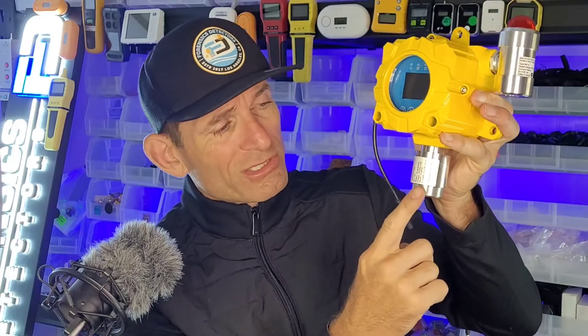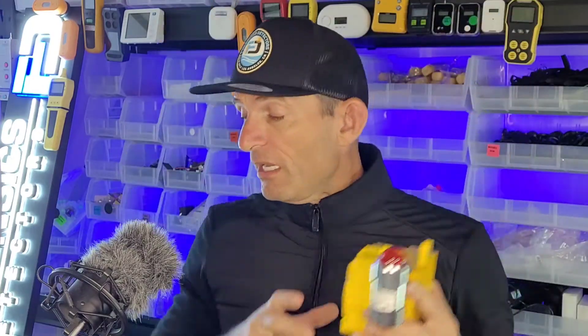The next product is specifically made for industrial use, for battery rooms — continuous monitoring using a very robust casing. The hydrogen sensor allows gas to diffuse in and detects the concentration of hydrogen, giving you a digital display and LED and buzzer alarm warnings. This is perfect for battery room hydrogen continuous monitoring. You mount it quite high because hydrogen is light and most often accumulates up high, though it depends on the ventilation system.